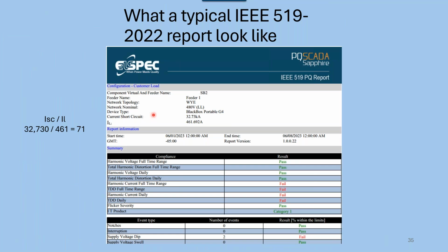You know, if you have a transformer, we could have a whole discussion on transformers. We do a ton in transformers: liquid, dry, cast coil. But basically, most of our transformers are 5.75% impedance. Some applications, because they want to limit fault currents, they'll go to like a 10%. All of a sudden, my regulation drops when I get into those systems. So the lower I can keep that impedance, the better. A lot of times you're just loaded at 100% of the transformer and you need a bigger transformer if you can put it in the application. And that'll stiffen the system. Or diversify the load, put it to another bank so you take some load off a transformer.